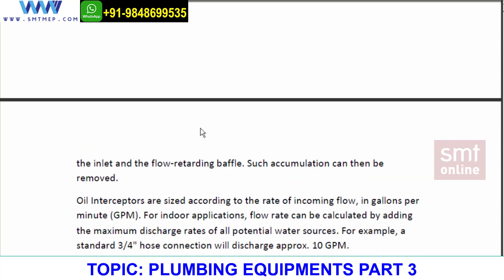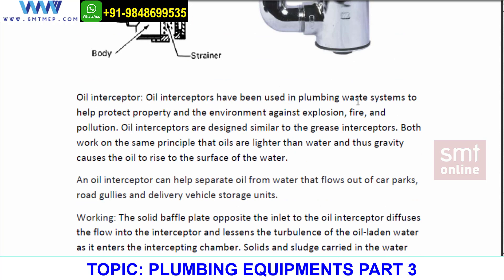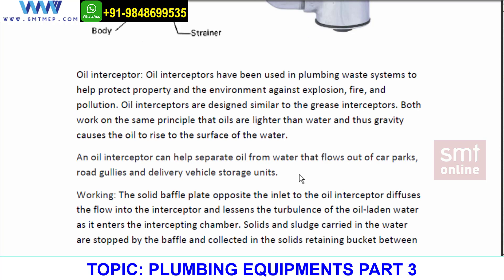Oil interceptors are used in plumbing waste and wastewater systems to help protect property and the environment against explosion, fire, and pollution. All oil interceptors are designed similar to grease interceptors — the mechanism is the same. They work on the same principle: oils are lighter than water and gravity causes the oil to rise to the surface. Oil interceptors can help separate oil from water flows out of car parks, road gullies, and vehicle storage areas.